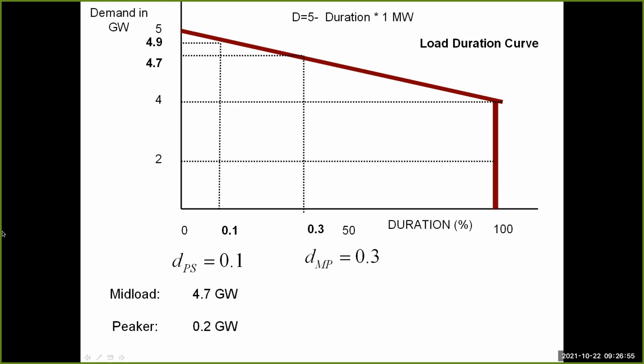This is used broadly. It's used for planning, of course. It's used in all kinds of analysis. It's used in a lot of the reports that you have for, okay, we want to have more renewables. How is this going to affect our system? The renewables are added basically to the load duration curve. And then we can see, oh, we need more flexible generation. We need much more, say, oil generators, usually much more gas-fired generators like open cycle gas turbine. Well, a lot of the base loads we're actually going to need less of.